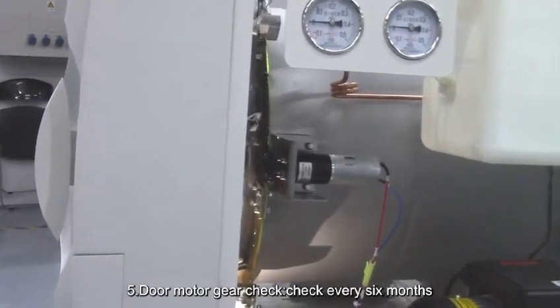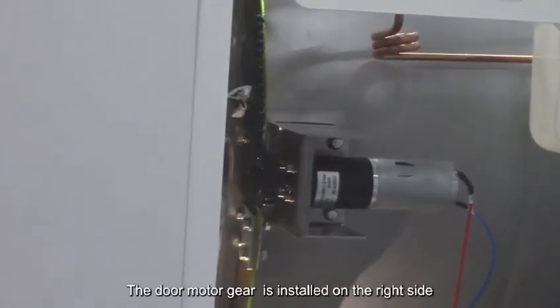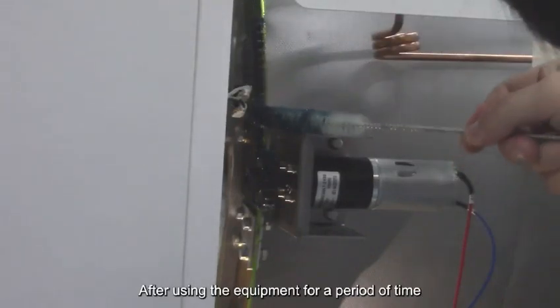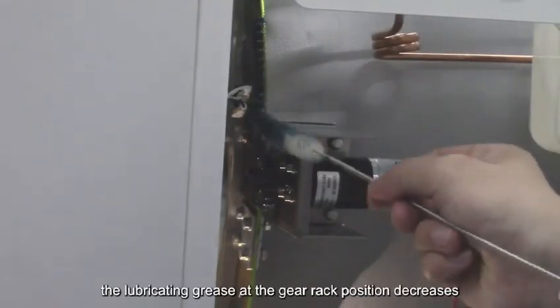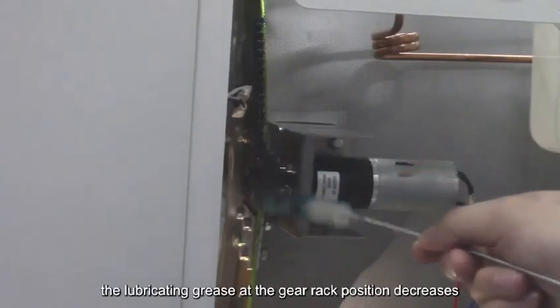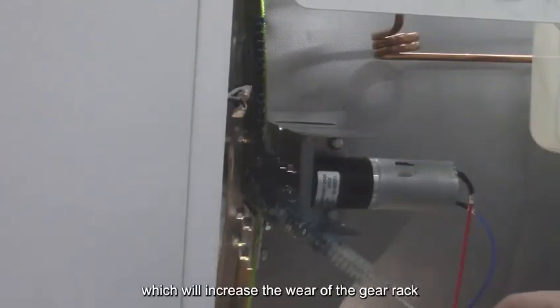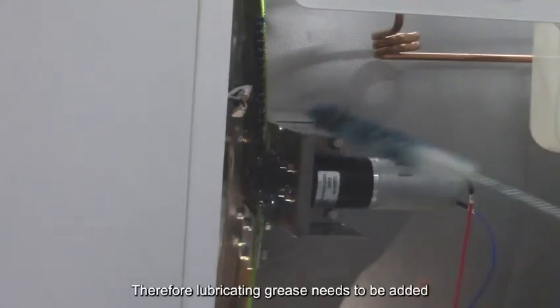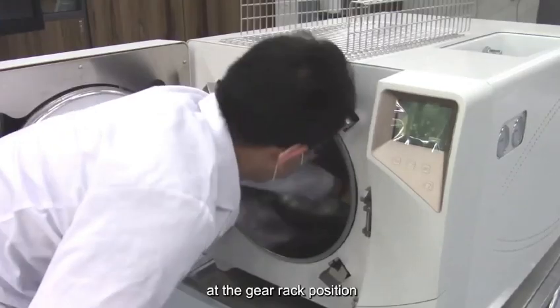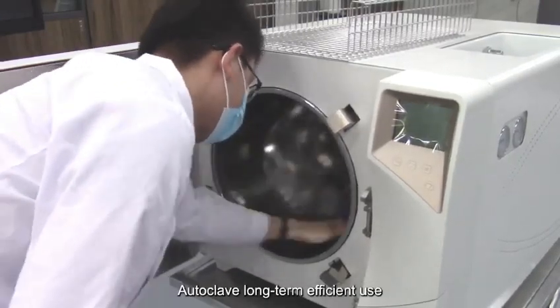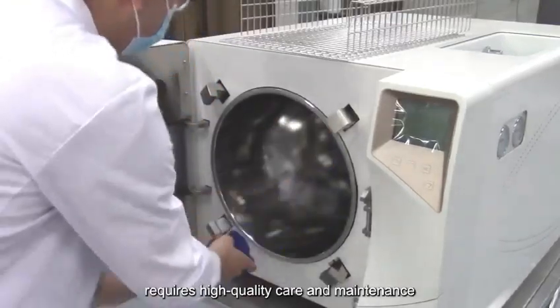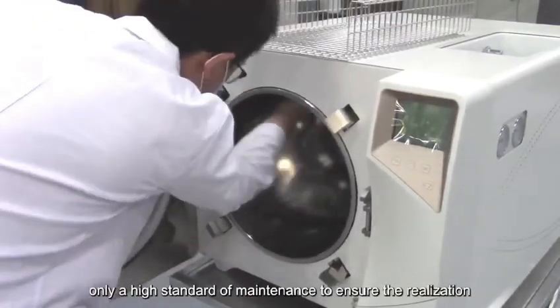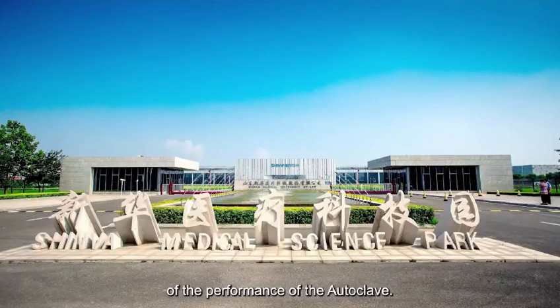5. Door motor gear check. Check every 6 months. The door motor gear is installed on the right side of the 60 liters and 80 liters equipment. After using the equipment for a period of time, the lubricating grease at the gear rack position decreases, which will increase the wear of the gear rack. Therefore, lubricating grease needs to be added at the gear rack position. Long-term efficient use of the autoclave requires high-quality care and maintenance; only a high standard of maintenance ensures the realization of the autoclave's performance.